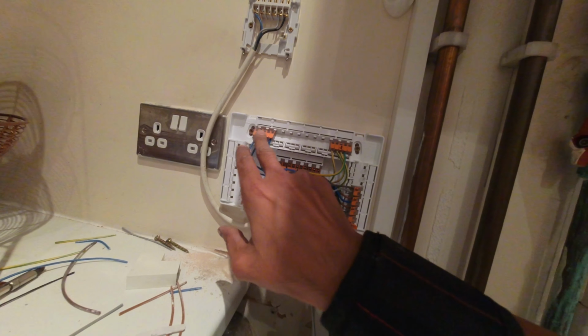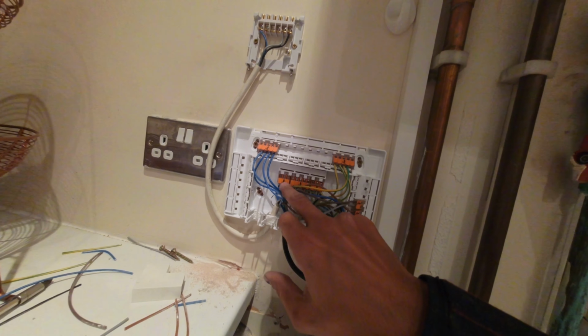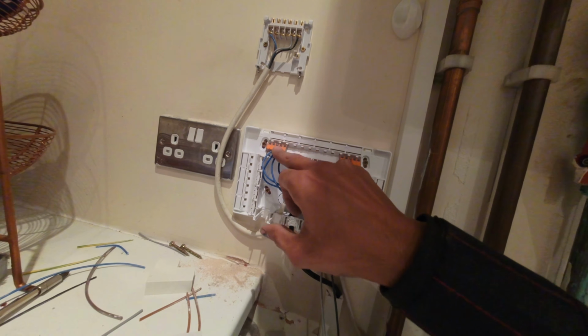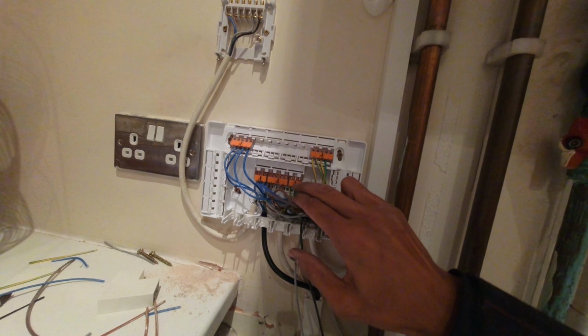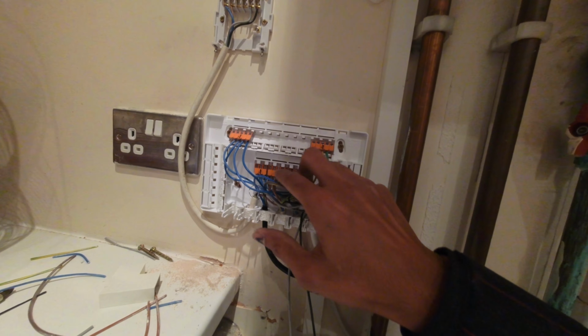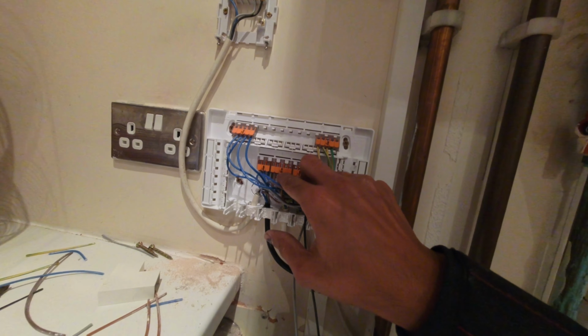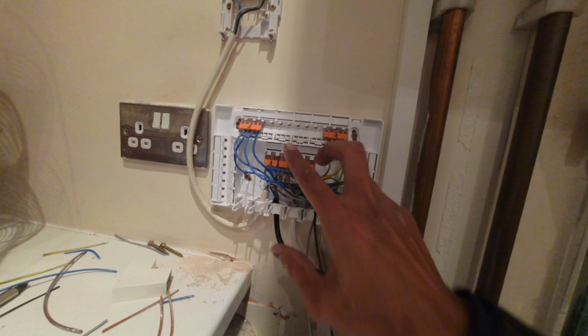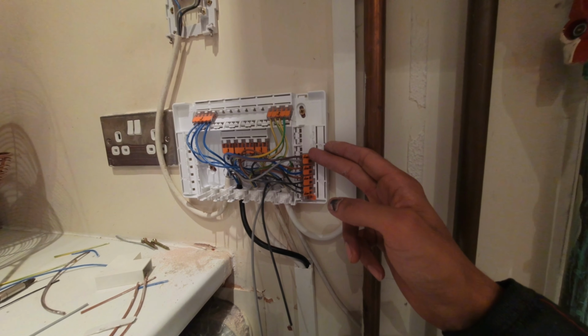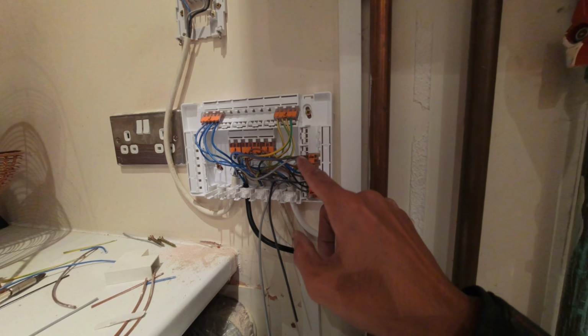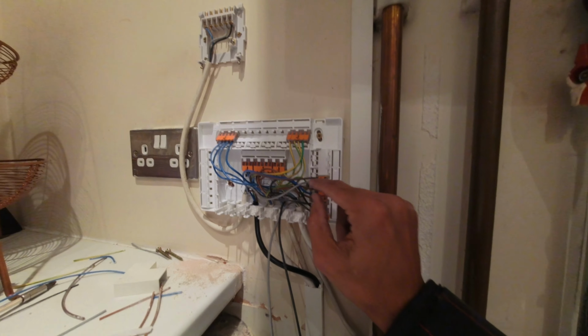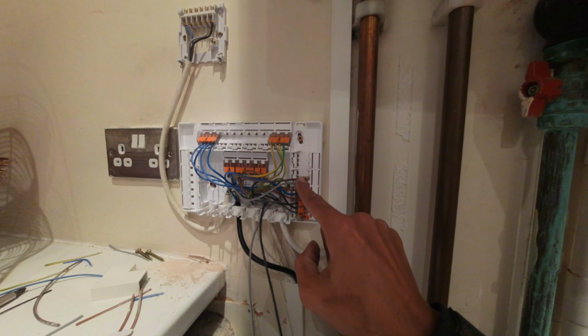So my wiring centre, I've got all my neutrals here. So I've kept that. You've got the neutral rail there, linking out to the neutral rail there. Got the earth rail there, linking to the earth rail there. I didn't need any more live conductors, so that 5-way was absolutely fine. And then on the right hand side here, this is my grey coming from there, so that's hot water on.